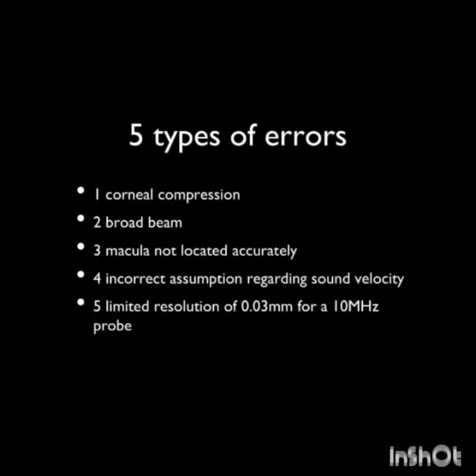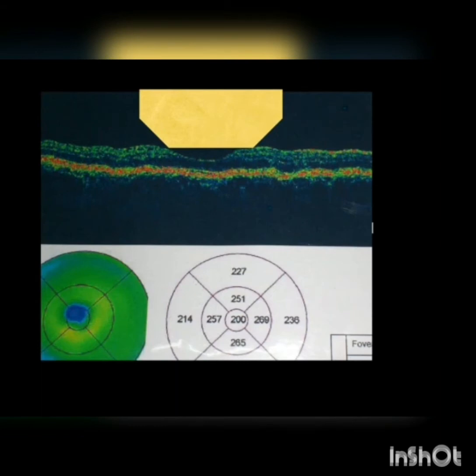While measuring axial length by ultrasound, there are five types of errors. The most important is variable corneal compression. The others are: a broad beam, the macula may not be located accurately, we may not be measuring the true refractive axial length, incorrect assumptions regarding sound velocity — important in very small and very large lenses — and limited resolution from using a 10 MHz probe. The broad beam of sound touches the macula and is reflected both by the humps and by the depth of the fovea; this difference can be close to 0.1 mm and can vary from patient to patient.